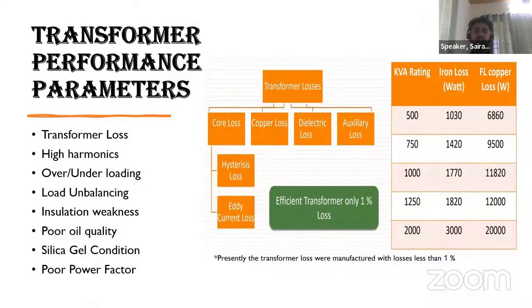Coming to the transformer performance parameters, the factors that affect the transformer's performance are transformer losses. We can categorize the losses into core loss and copper loss. Core loss is further divided into hysteresis loss and eddy current loss.